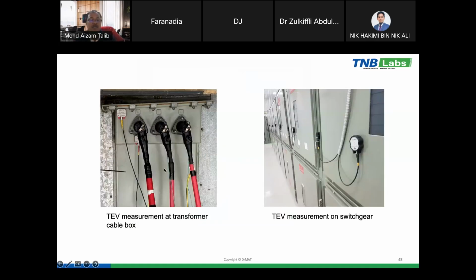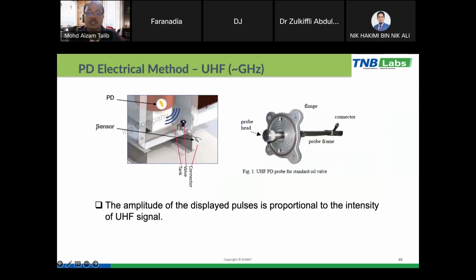So this is an example of the TEV measurement on the transformer cable box. It can only be applied if the insulation used is air. So when we use gas or liquid, we are not able to use TEV. We need to use other sensors, for example, HFCT and also UHF sensor. And then this is an example of the TEV measurement on the switchgear.